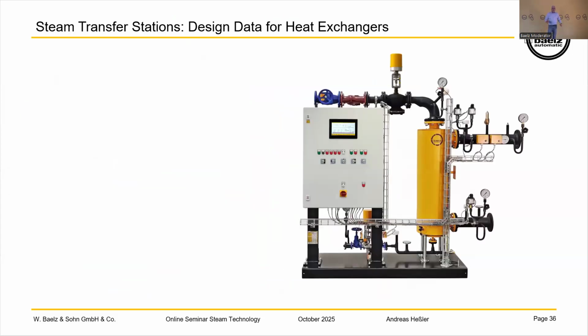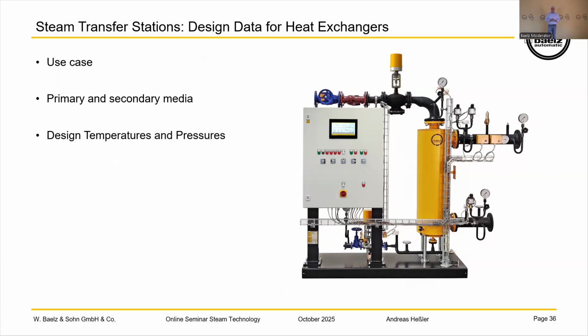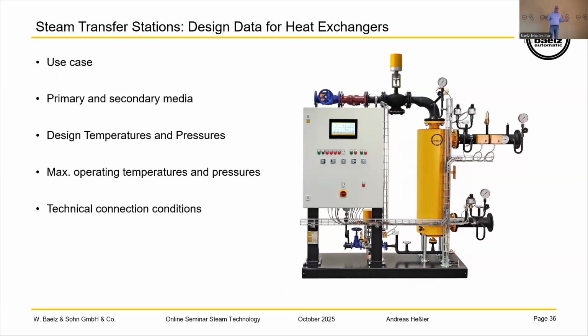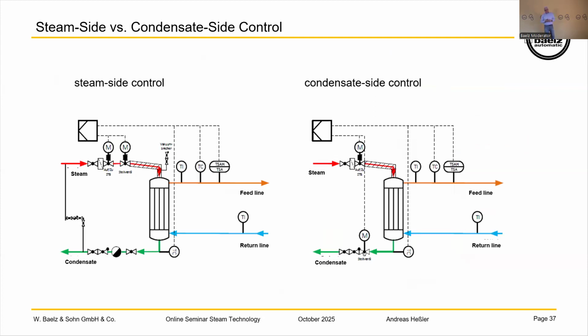Let's say something about steam transfer stations and what kind of design data we need. First, we need the use case: what do you need it for? Then we need the primary and secondary media, like steam or water. The design temperatures and pressures, and the maximum operating temperatures and pressures that the heat exchangers handle. Technical connections and conditions, and the type and design of the control. That means whether you want a steam side control or a condensate control. I will now show you the difference between steam side control and condensate control.